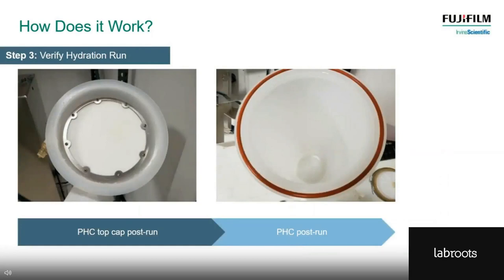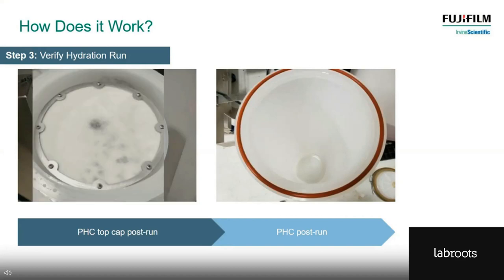As that powder comes out of the top of the cartridge, it goes along the top line on the skid and goes to a sterilizing-grade filter. So at the same time as you're hydrating, you're also sterilizing the media. Then the secondary hydration cartridge activates, which contains all components that don't dissolve well at neutral pH — usually things like some of the amino acids Tom mentioned, or possibly iron. We create the appropriate environment within that chamber to dissolve those, directing them into the main chamber and through the sterilizing-grade filter to produce the media.